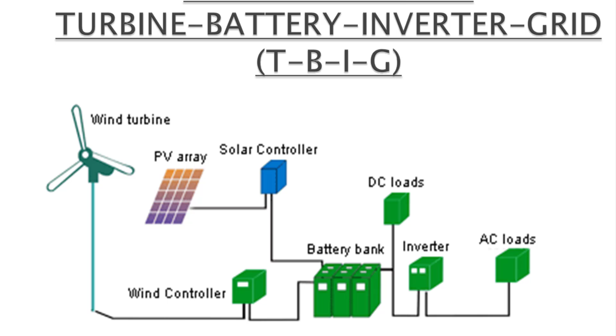So I came across one tentative model. The tentative model consists of a wind turbine and solar, connected to controllers. You can see from this graph, the wind turbine is connected to a wind controller and solar power is connected to a solar controller. Thereby it is connected to a battery bank. After the battery bank, it is connected through an inverter to an AC load. The inverter is used to convert from DC to AC, because battery storage is DC. If there is any non-linear power generation in the generation part, or any spikes in the load side, then automatically, with the help of a controller, which consists of a PID and FOPID, which I will explain in the later part.